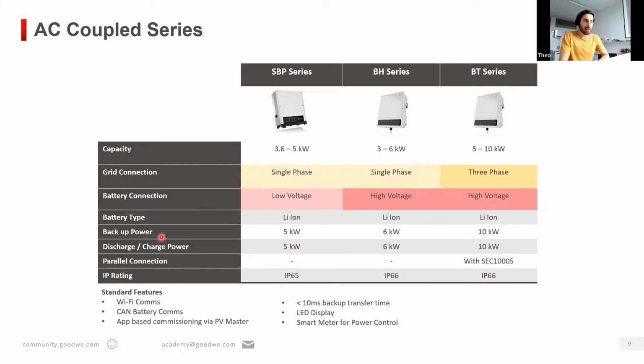Also good to know is that the backup power of these inverters, sure, there are some limitations. You cannot connect too big of a load because the inverter can only power so much. You're also not allowed to connect any loads with high inrush currents or any inductive loads. But as you see here, the maximum capacity you can connect on the backup side is the same as the rated power of the inverter. So a 6 kilowatt BH inverter can have 6 kilowatt on the backup side connected. Apart from that, all inverters also have an IP65 minimum rating, and some of them, like the BH, the BT, and the EH and ET series, have even IP66 rating.